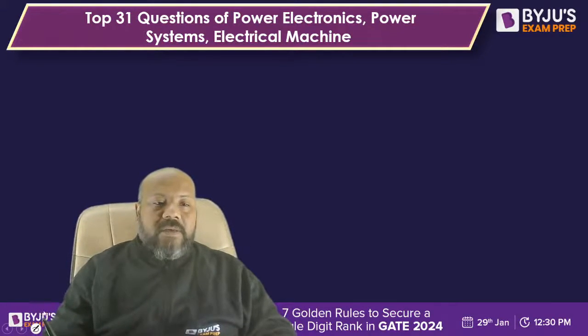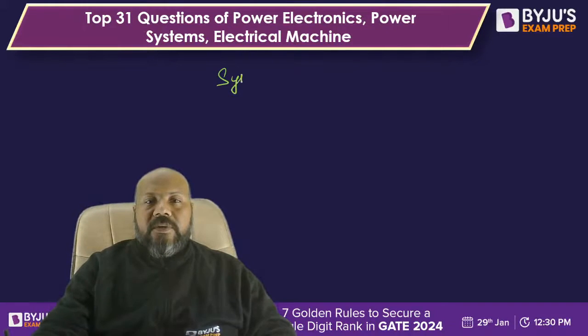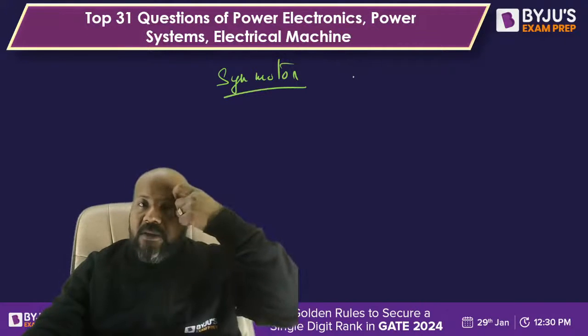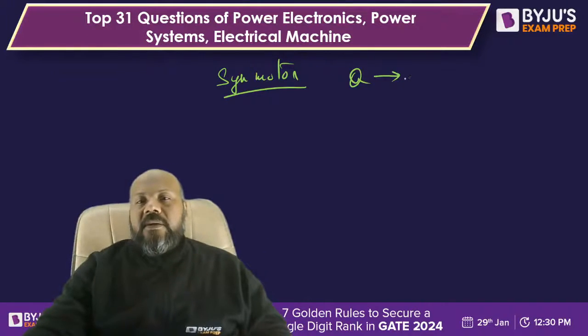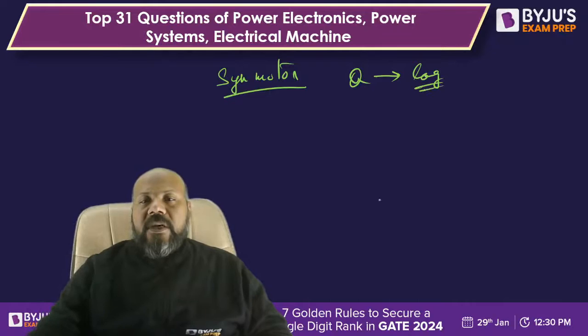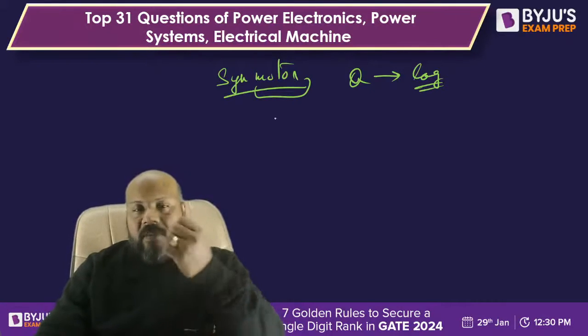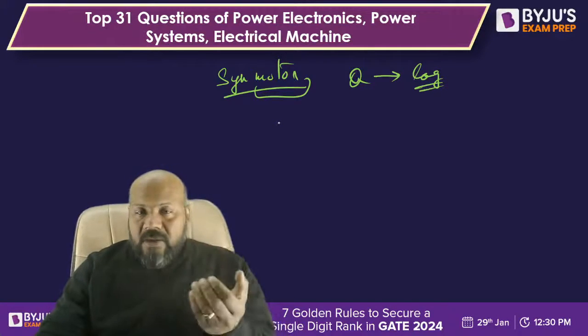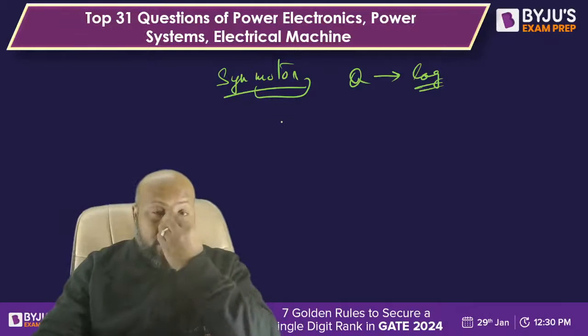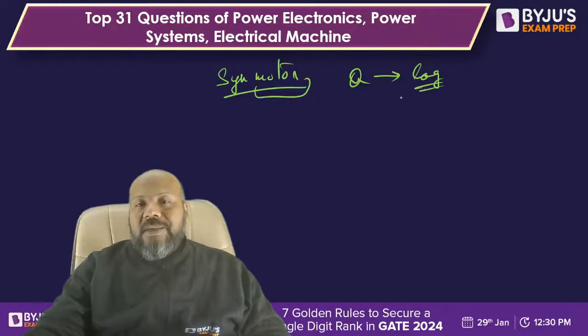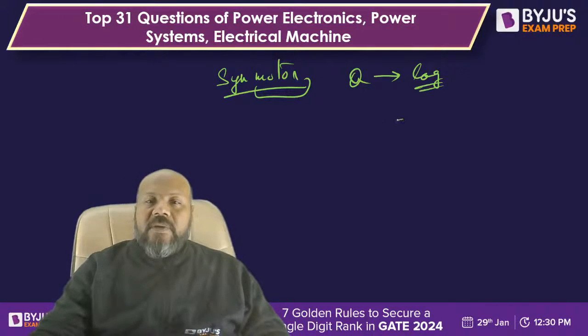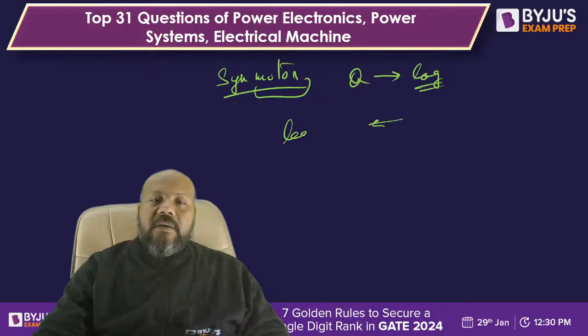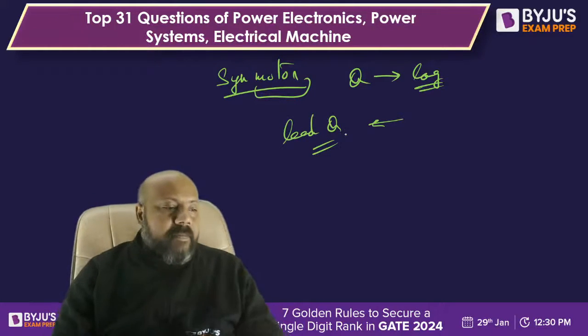So what I was saying, a Guru Mantra for synchronous motor: synchronous motor is supplying reactive power. Which type? Lagging reactive power. What is the nature of the motor, to supply or to absorb? The nature of synchronous motor is to absorb power, but it is supplying lagging reactive power, which means it is taking leading reactive power.